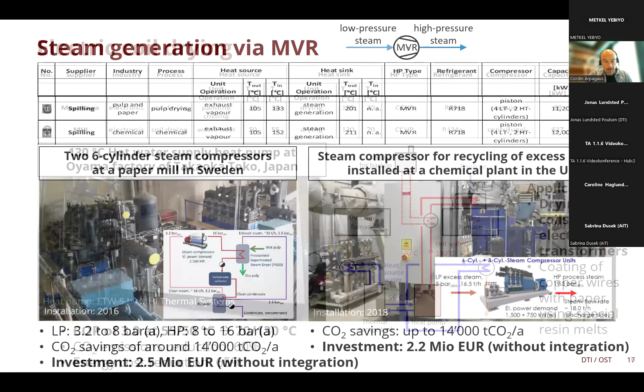The next demonstration case shows steam generation via MVR technology from Spilling, which has piston compressors with multiple cylinders. So low pressure steam is upgraded, or recompressed, to high pressure steam. The left example shows a 6-cylinder steam compressor at a paper mill in Sweden. And the right example shows a steam compressor for recycling excess steam in a chemical plant in the UK. It shows a double stage steam compression with a 6-cylinder steam compressor. Here the steam is compressed from 5 bar absolute to 19.5 bar, and the capacity was 11 megawatt.